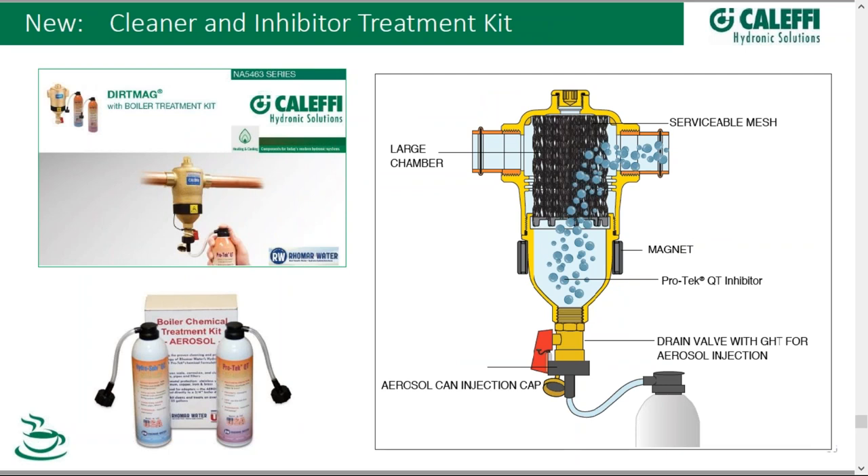Caleffi offers a cleaner and inhibitor treatment kit, basically sold with our very popular DirtMag magnetic dirt separators. This is an aerosol type of chemical kit — it has both a cleaner and then an inhibitor, injected into the system by way of a garden hose type connection at the bottom of our dirt mags. These chemicals are from Rhomar — we don't make these chemicals ourselves. Rhomar is a very proven, high-quality producer of both cleaning and inhibiting chemicals for the hydronic industry.